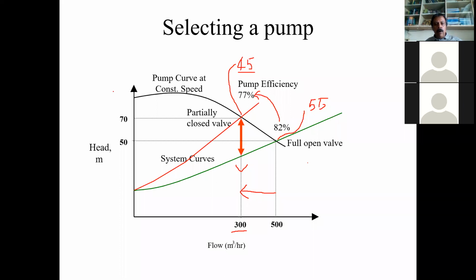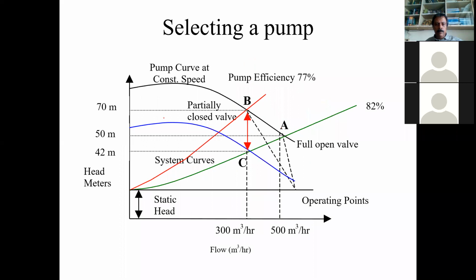Now, what are the options? Suppose we had gone in for a smaller pump, say a 300 meter cube per hour pump. Then the pump curve would have been this blue curve, exactly cutting the system curve at this point, delivering 300 meter cube per hour. So if this was the case, then here it would have been 55, this would have been 45, and this would have been maybe 30 kilowatts. So we should have been drawing only 30 kilowatts, ideally, if we had properly selected the pump.